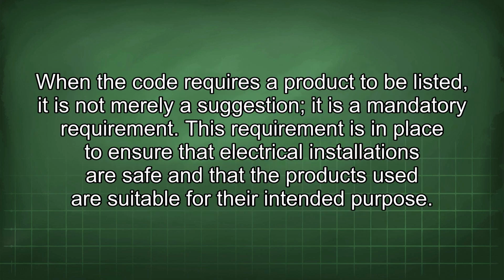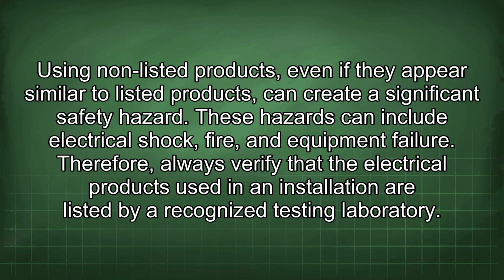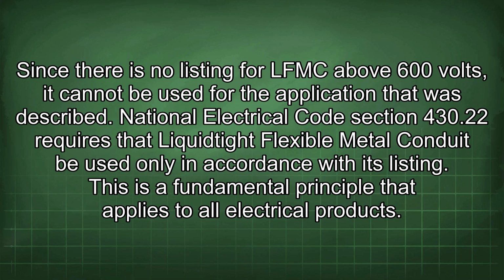When the code requires a product to be listed, it is not merely a suggestion, it is a mandatory requirement. This requirement is in place to ensure that electrical installations are safe and that the products used are suitable for their intended purpose. Using non-listed products, even if they appear similar to listed products, can create a significant safety hazard. These hazards can include electrical shock, fire, and equipment failure. Therefore, always verify that the electrical products used in an installation are listed by a recognized testing laboratory. Since there is no listing for LFMC above 600 volts, it cannot be used for the application that was described.